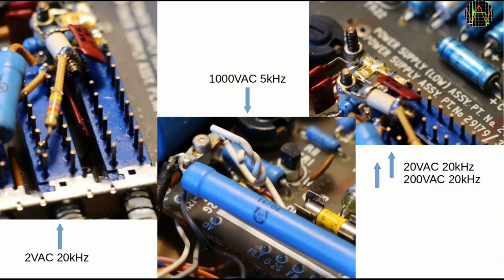Now for the higher frequencies. This is done using trimmer capacitors. The trimmer for the 2 volt range is a trimmer mounted horizontally over the range switches. Despite the service manual stating that this calibration should be done after the meter is back together, but not in the housing yet, I found this to be impossible in practice. You basically have to squeeze past the front plate holes for the switches and then try to find that trimmer screw far in the back. Okay, maybe it can be done if one had a very special non-metallic, extra long and extra thin screwdriver. I don't, so this has to be done while disassembled, even though without being properly back together, the calibration may actually be slightly off.